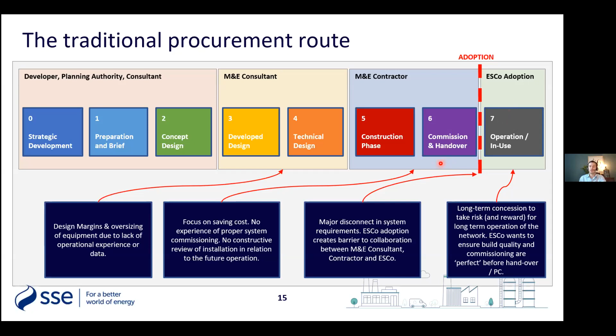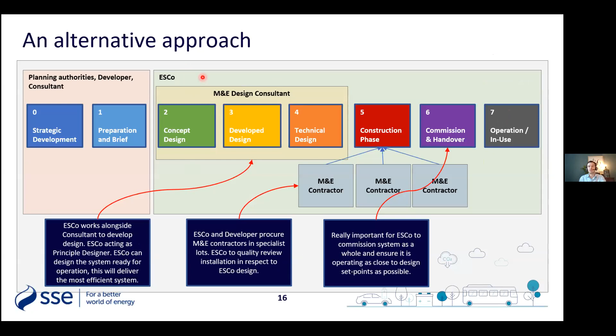It isn't the best model, because I can remember one of my first ever networks. We adopted this network, and we were only brought in the day of practical completion. So the M&E contractor wanted to get off site, and you start having this big barrier to ESCOs adopting, because if we're about to take on the risk for 25 years, we want to make sure the whole thing's working correctly, which comes down to commissioning, and not just commissioning a system as a whole. Unfortunately, I don't think I've got time to discuss that. But this would be a plan for the future, just bringing that ESCO in at an earlier stage, because they will take risk on the design. They're not saying they're going to do the design, but they will take diversity risk, sizing risk, and that's a really important point.